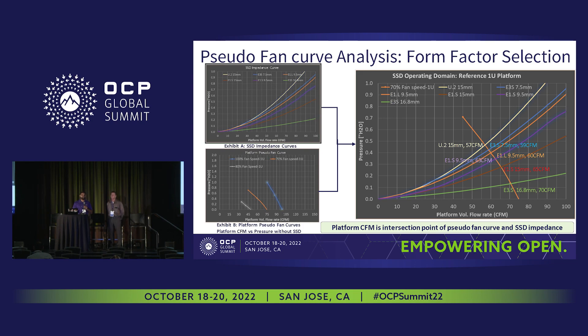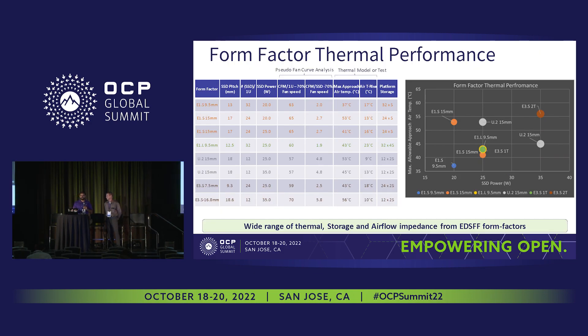U.2 has very high impedance — 18 millimeter pitch, 15 millimeter drive — resulting in the lowest airflow through the fan at 70% fan speed. We are going with an ISO fan speed comparison. E3S has lower impedance and brings more airflow through the platform. E1S 15 millimeter has even further lower impedance because of the fins and structure, so it brings even higher airflow. We made a matrix varying the power, covering E1S, E1L, U.2, and E3S form factors.